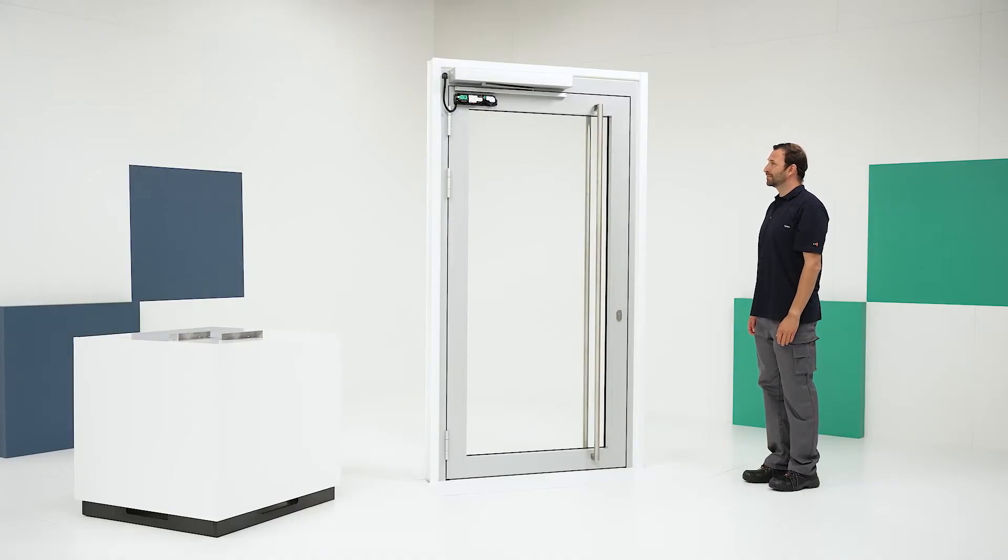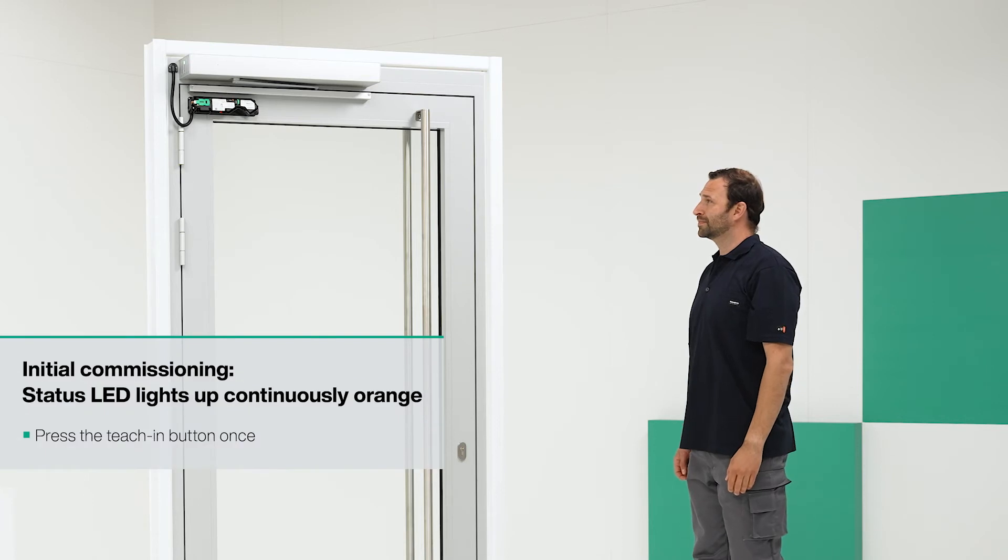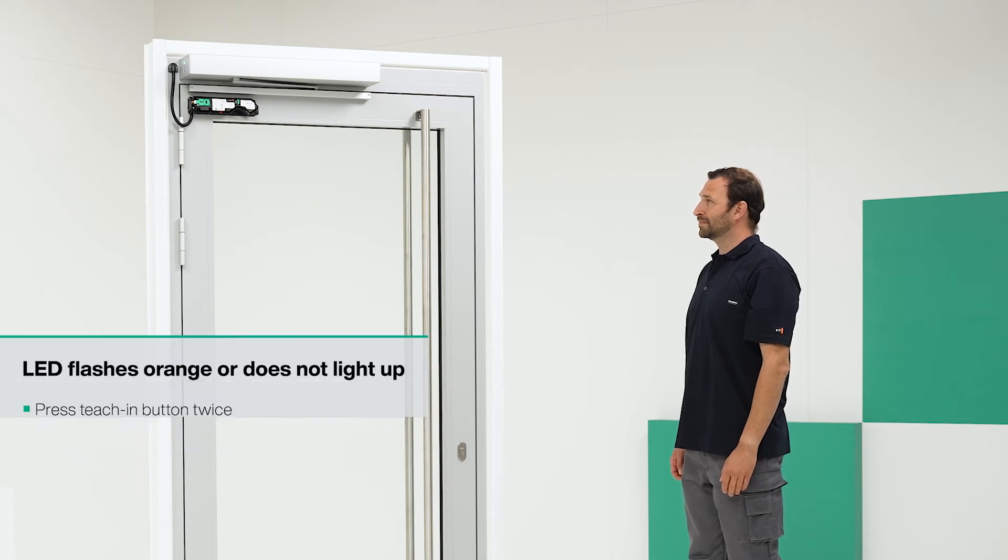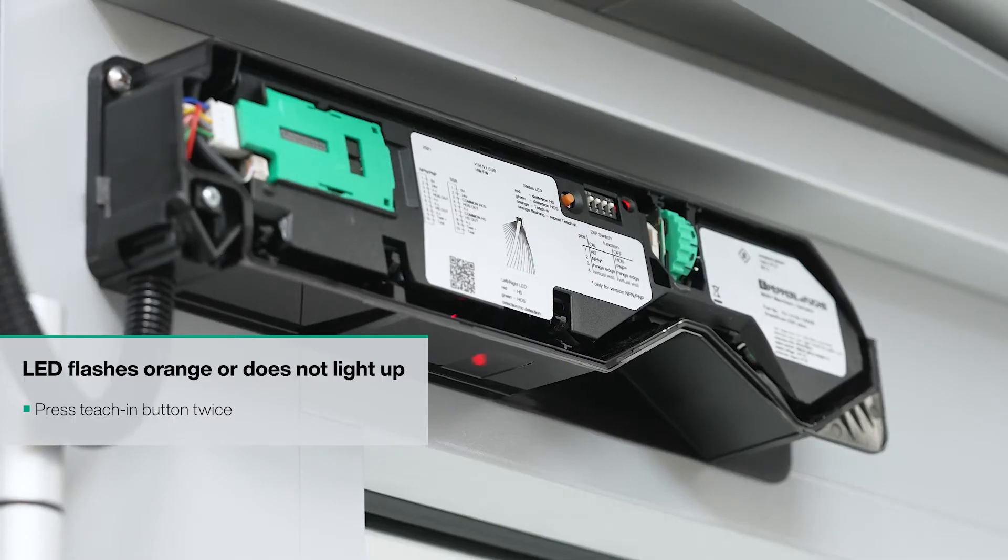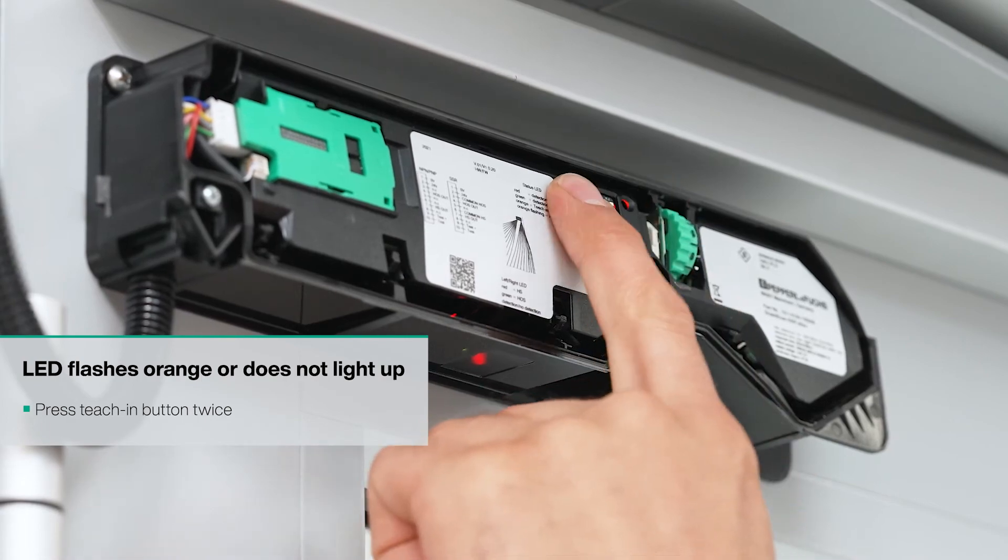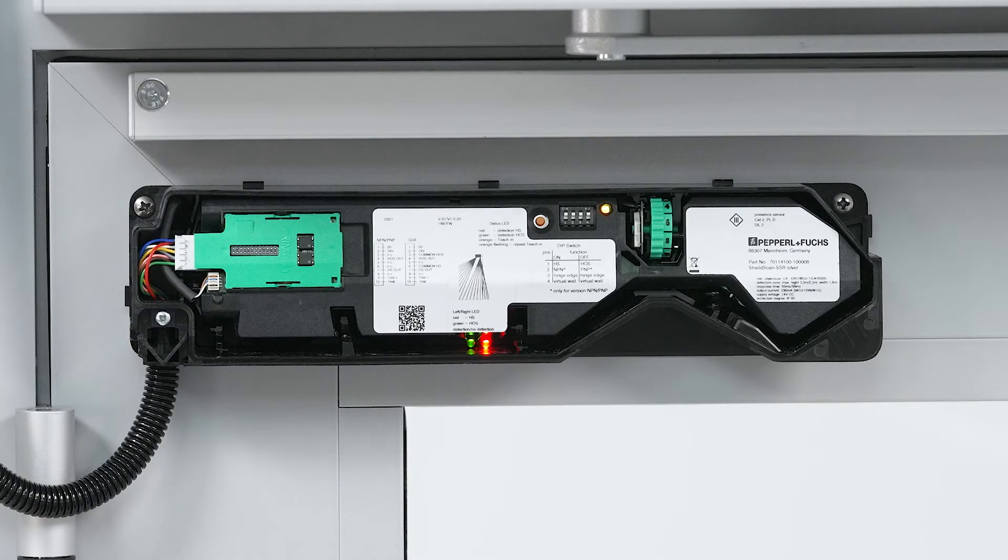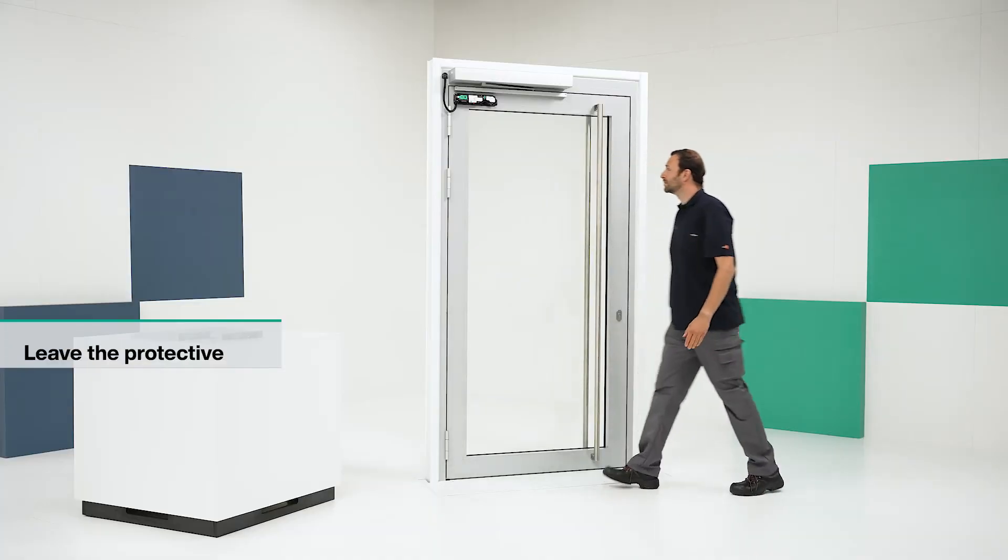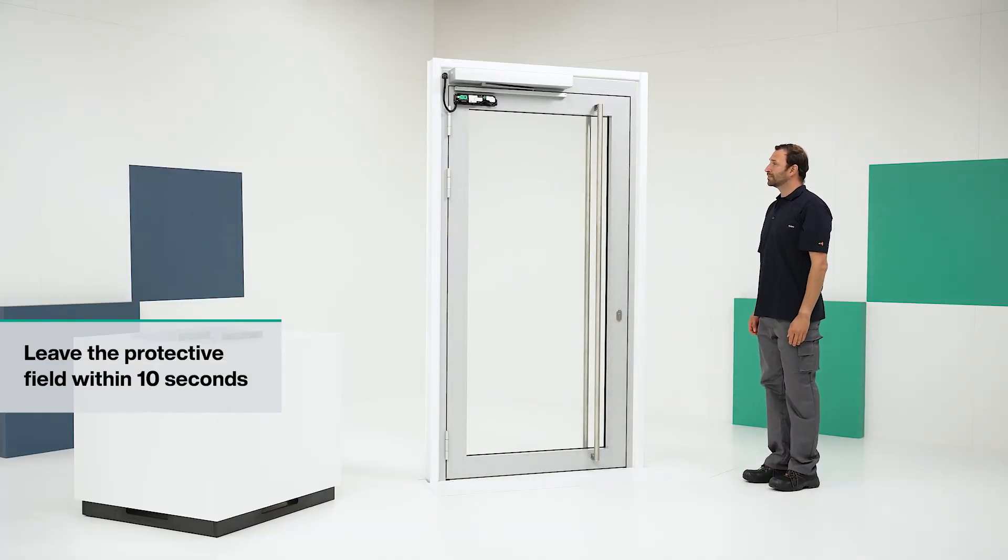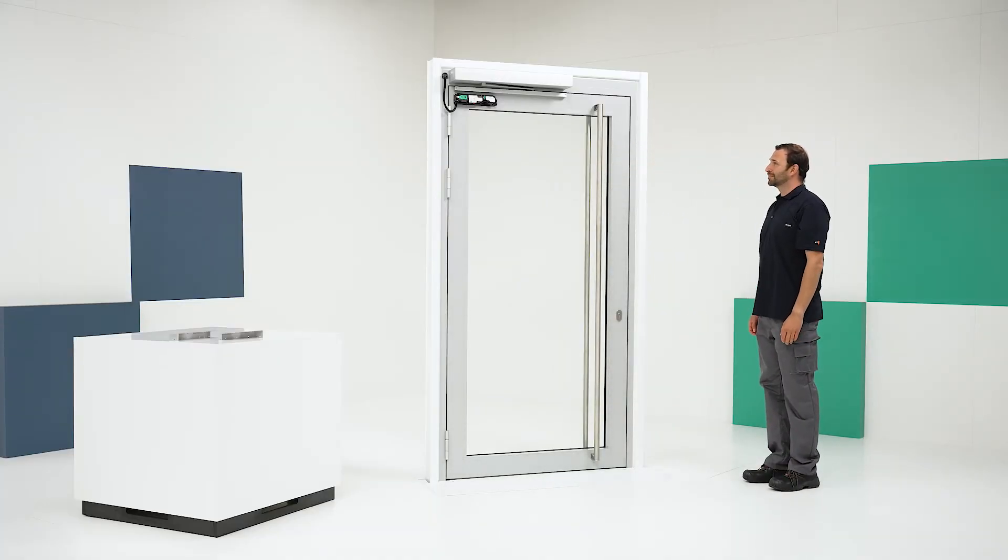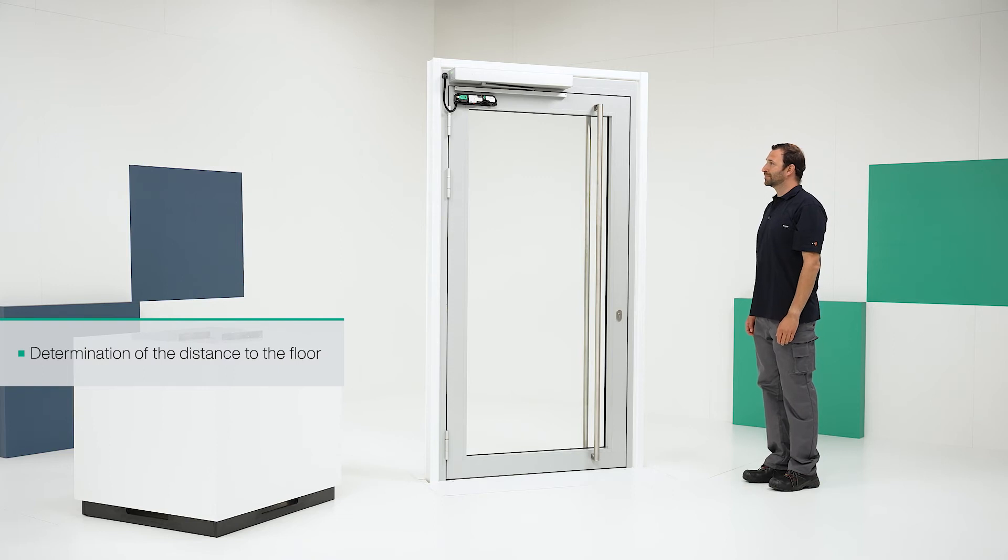If this is the initial commissioning of the shield scan, the status LED lights up continuously orange. In this case, press the teach-in button once. If the LED flashes orange or does not light up, press the teach-in button twice. The status LED will now begin to flash green and red alternately. Once this happens, leave the protection field within 10 seconds so that the sensor can automatically determine the distance to the ground.